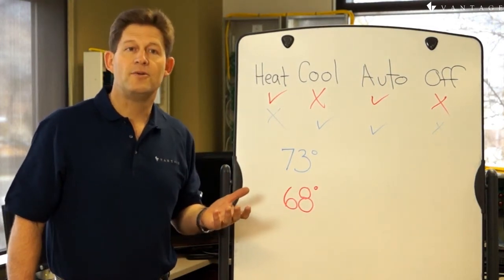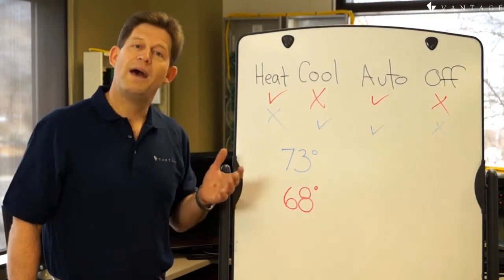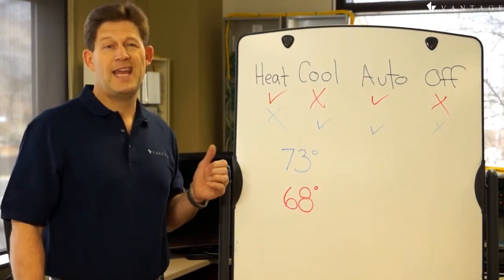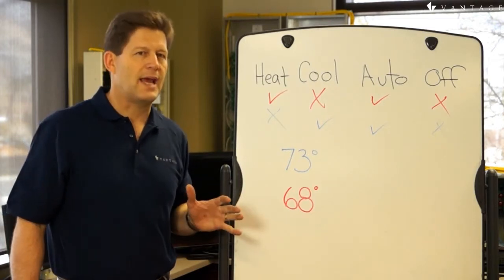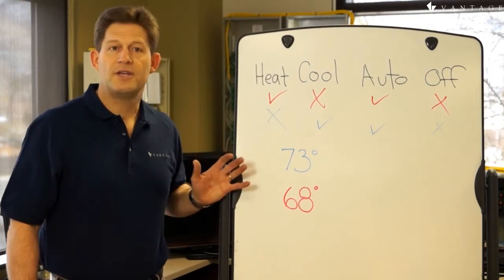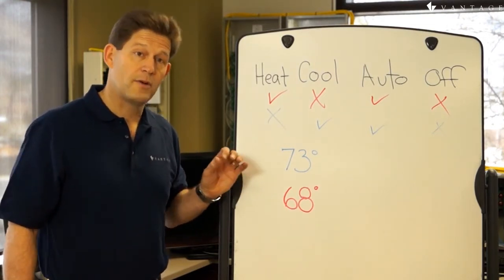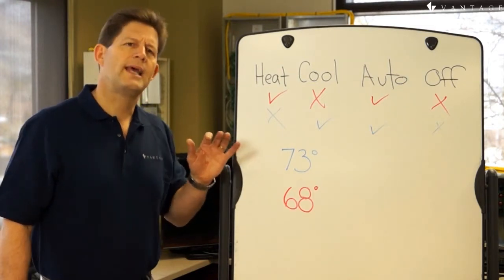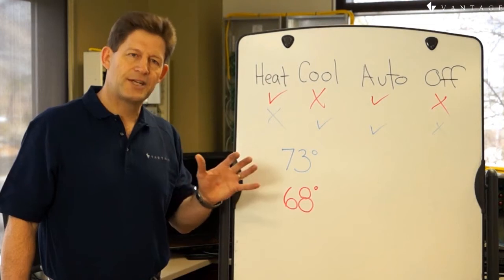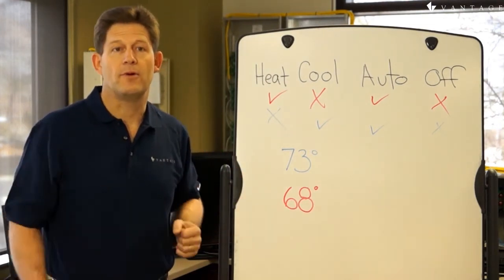This is particularly true in regions where there's a wide temperature fluctuation, like in the high desert of Utah where a 30-degree temperature variation is not unheard of. When we have a wide daily temperature swing, it's highly likely that both heating and cooling are going to run the same day if we select auto mode, which to many will seem wasteful. To save energy, we might leave it in heating mode to get the home comfortable in the morning, and then circulate air from outside later in the day to cool naturally, instead of having competing forces working against each other.